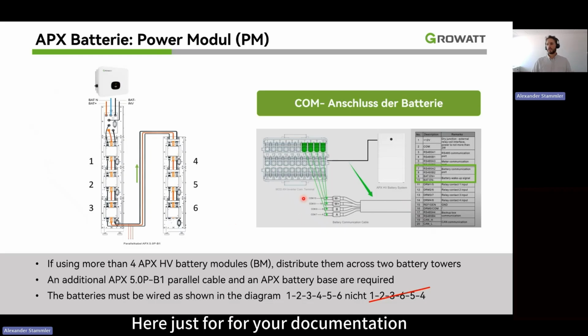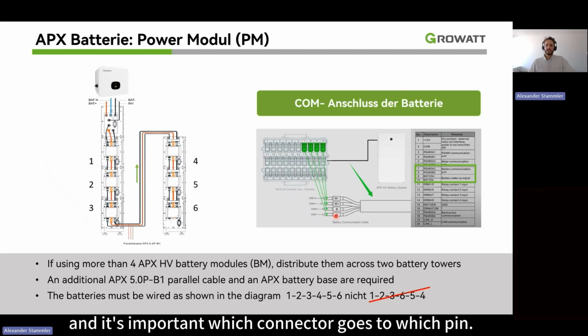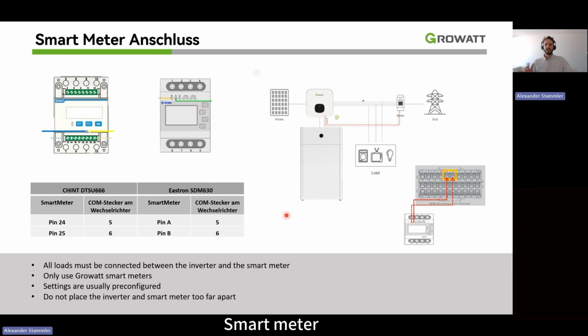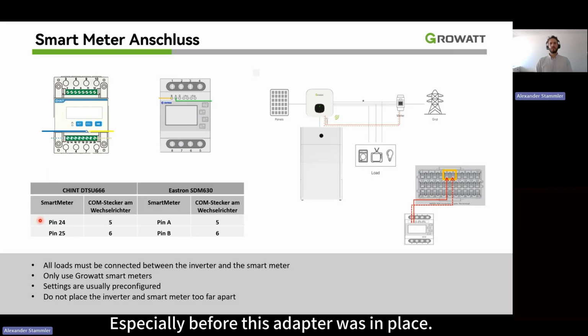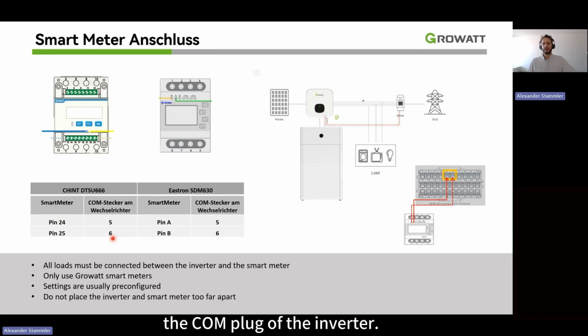Here, just for your documentation, you have again the different connectors, and it's important which connector goes to which pin. Smart meter, we often have issues with that in the field because, on the one hand, it's been wrongly connected, especially before this adapter was in place. We often had that pin 24 on the Chint, for example, was connected to pin 16 on the COM plug of the inverter. So you can see it here if you ever have an issue.